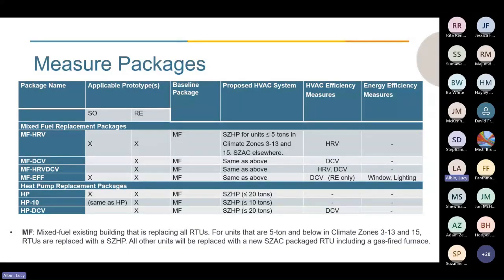First, we wanted to consider HVAC-related measures only, and we determined these to be HRV and DCV, which we analyzed both separately and together. And the reason for this is that the assumptions for the small office prototype do not contain any units serving zones with high occupancy spaces, such as conference rooms, and the occupancy profile is otherwise relatively flat, so there weren't opportunities for occupancy-based savings there. So we wanted to present both with and without the DCV.